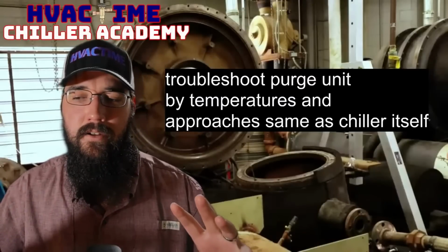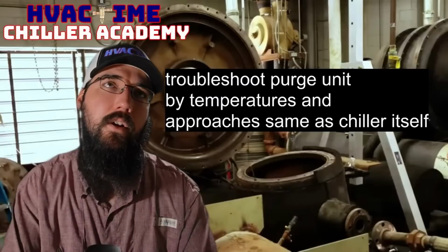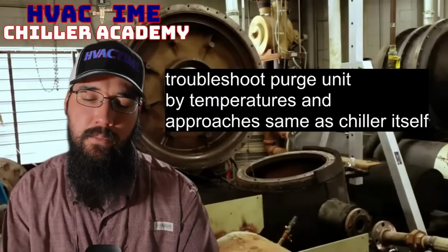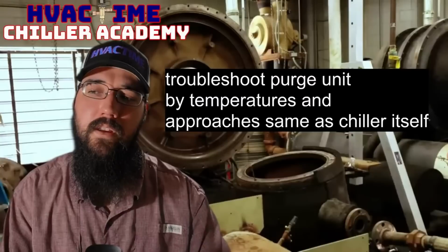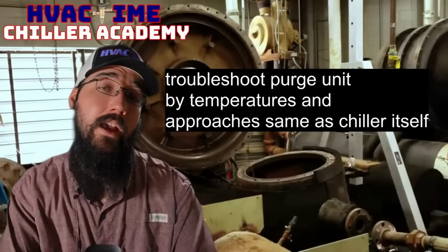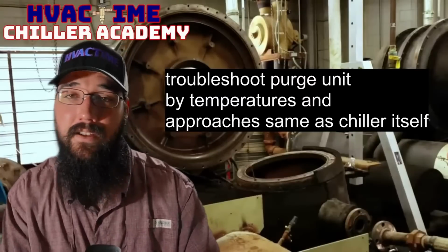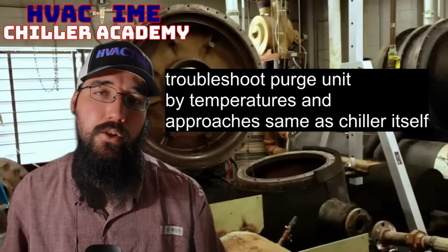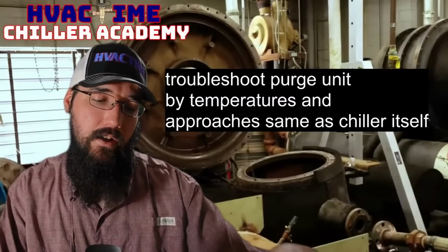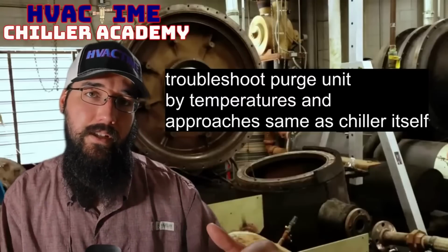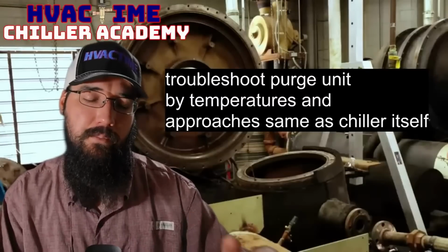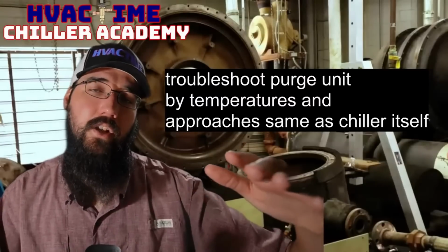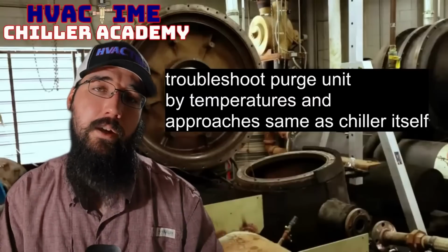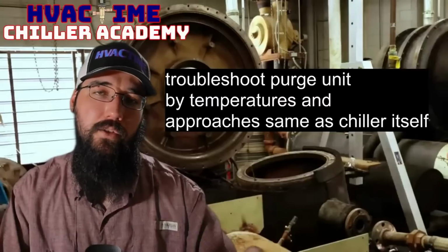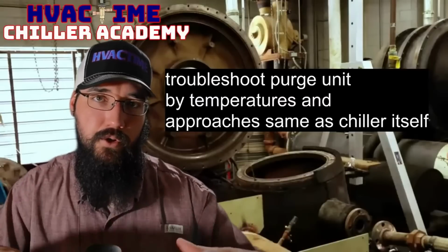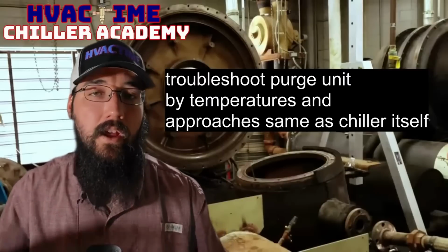Then I'll start looking into other factors such as what is my liquid line temp, what is my discharge temp, what are my suction temps doing, what is the temperature coming through the metering device, is the metering device metering. I should be able to isolate the refrigerant from the tubes from the chiller's condenser, not the purge unit, and see that suction temperature drop because I'm going to have very little load in that purge after a few minutes. So there are some of those things I can do to troubleshoot the purge unit itself to see if it's a metering device or otherwise.